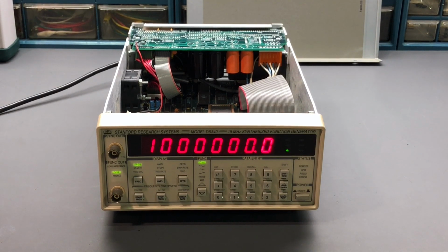So at this point, I'm going to let the instrument run for at least a half an hour, maybe even 45 minutes or so. And I will also put the top cover on it. It needs to come up to just a normal operating temperature before any adjustments are made to the calibration for any of the settings. You don't want to do any calibration on the instrument while it's cold, because as it warms up, particularly the crystal oscillator will change just a little bit in frequency. So it needs to stabilize. So I will let it run here, and then when some time has gone by, I will continue on.